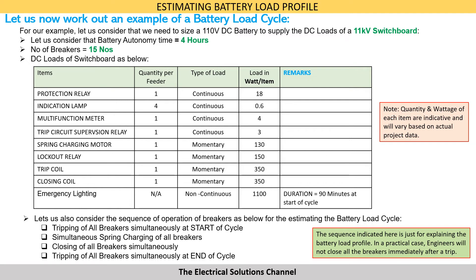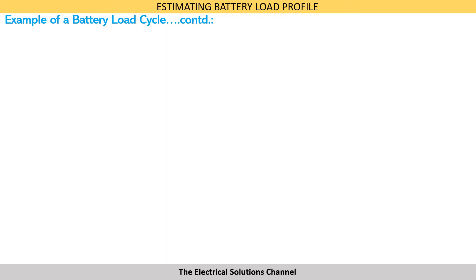Please note that the sequence indicated here is just for explaining the battery load profile. In a practical case, engineers will not close all the breakers immediately after a trip without identifying the cause of all breakers tripping simultaneously. We can now calculate the loads on the battery bank.